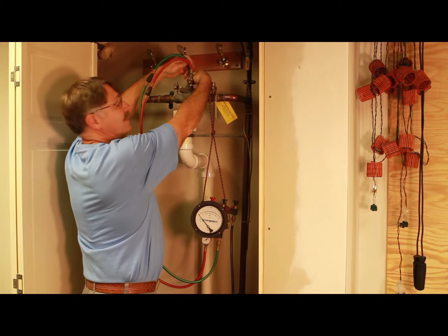Okay. So I have to fill the test device with water from the backflow. Okay, so I'm actually testing the pressure across the first. This, like the other one, has two check valves in it. One's located here, one's located here, and where that other one just had that cage in the middle that just held the two checks where they belong, in the middle of this one there's actually a relief vent. So part of the test on this is actually the testing that it relieves at the proper pressure. So here we go. And this one actually failed.